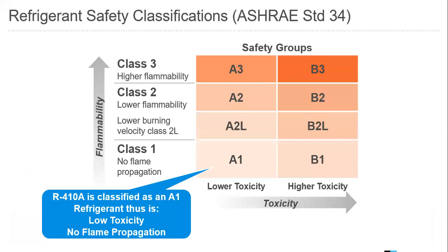Within ASHRAE 15, or actually ASHRAE 34, it defines the classification of refrigerants. So we actually have 3 different classes. Class 3 is high flammability. Class 2 is lower flammability. And Class 1 is no flame propagation at all. And then there are actually 8 different safety groups.